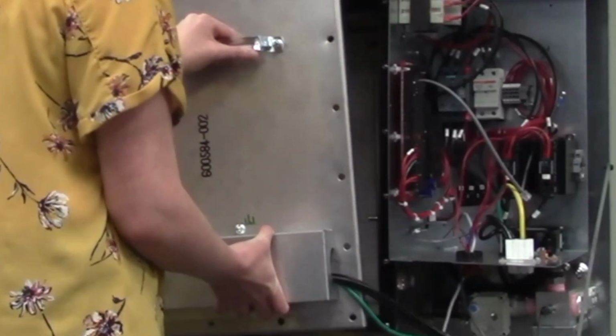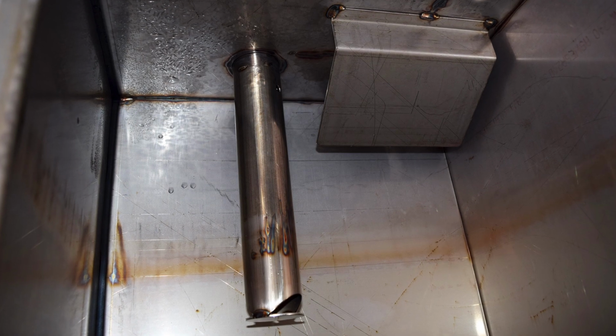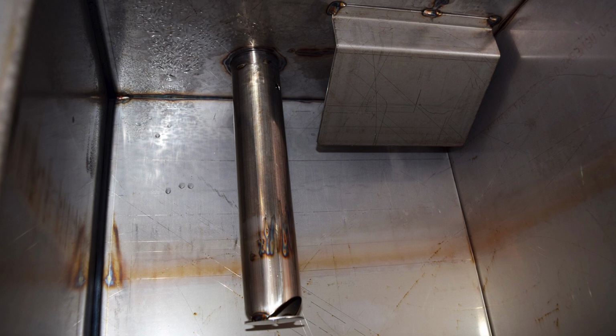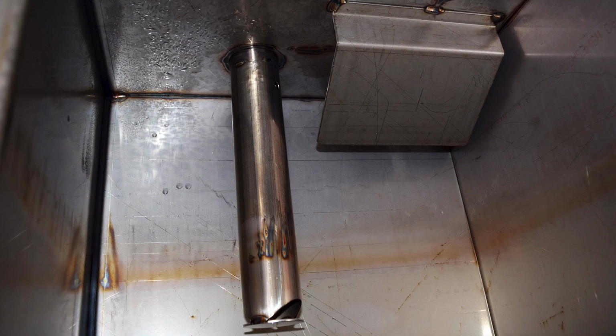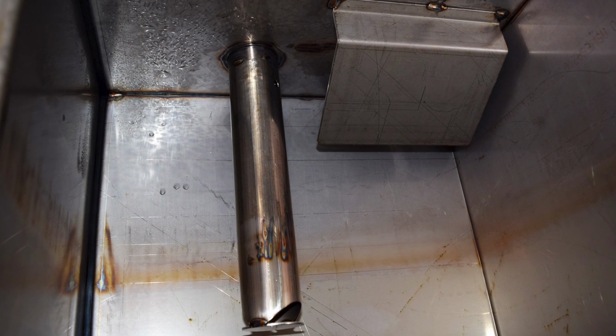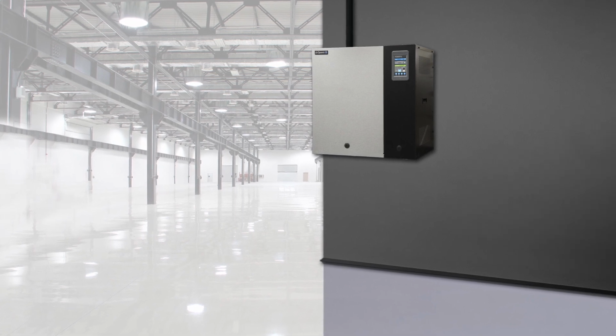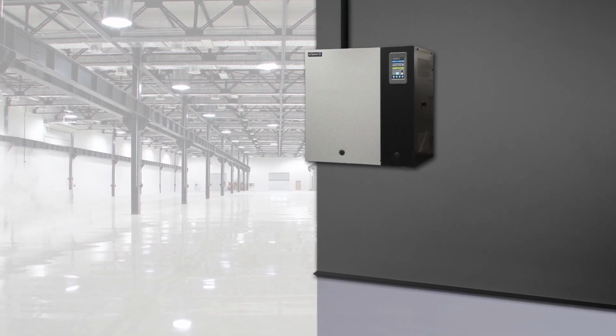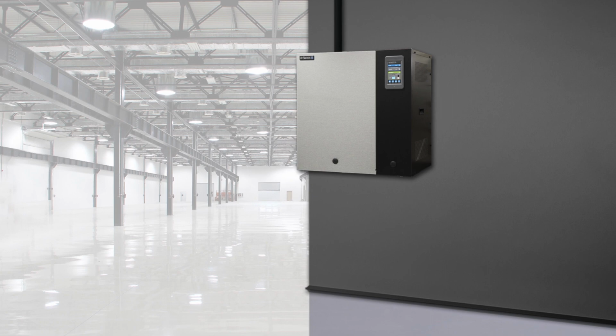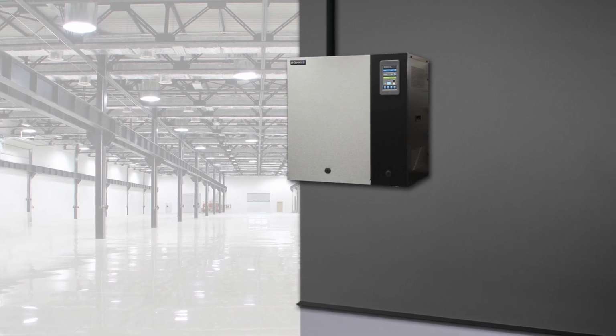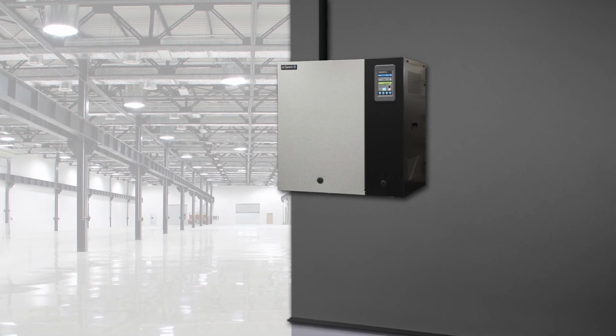The best way to determine how often your humidifier needs maintenance is to remove the tank cover and inspect it for mineral deposits after 3 months of duty. Hours of operation and duty cycle will determine your maintenance schedule, as will water quality. Now you are ready to perform routine maintenance of the RTS Humidifier RX series. Taking time to plan and perform maintenance on a regular schedule will keep the equipment up and running at peak performance for many years.